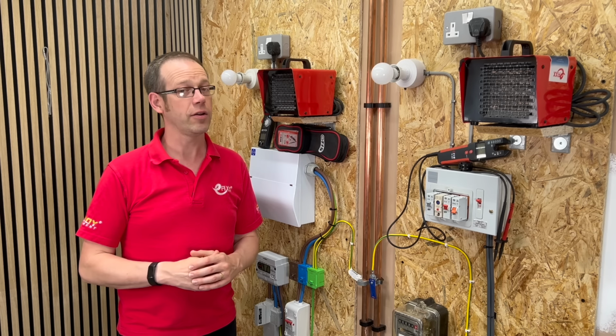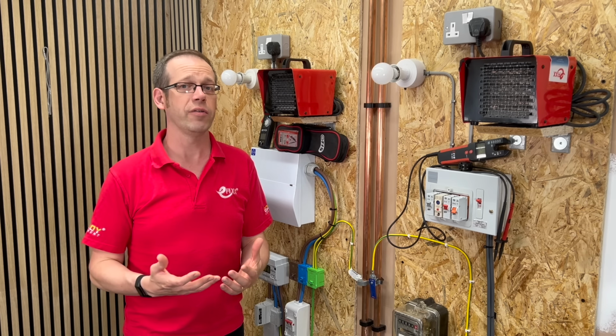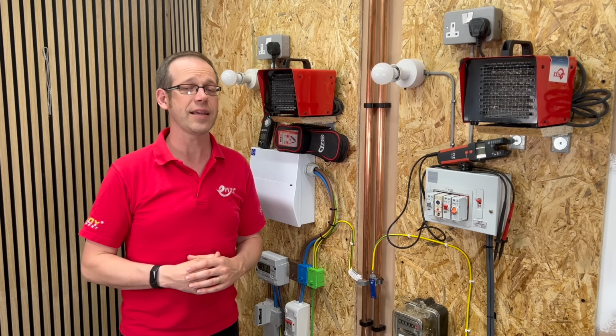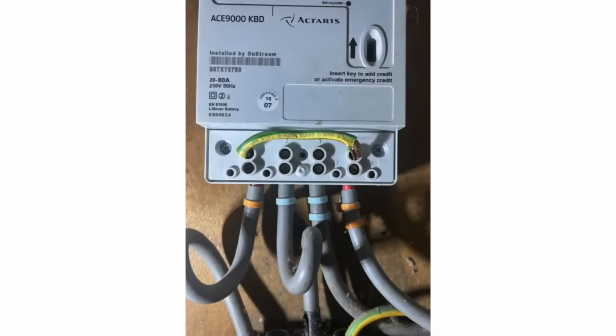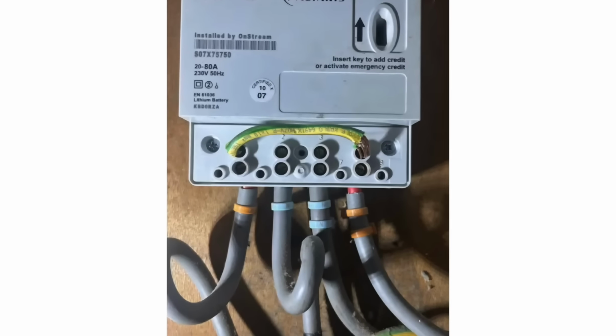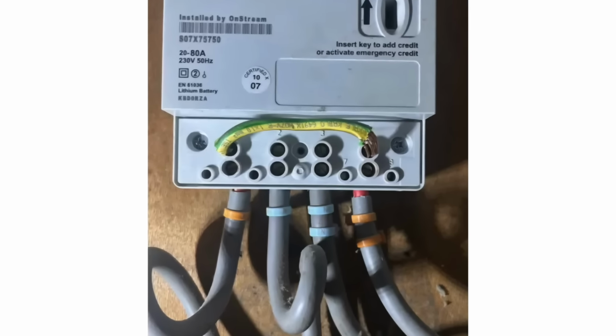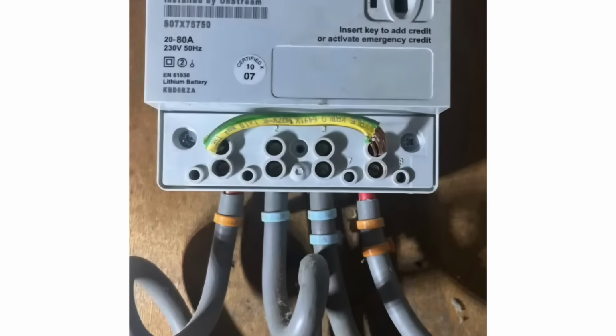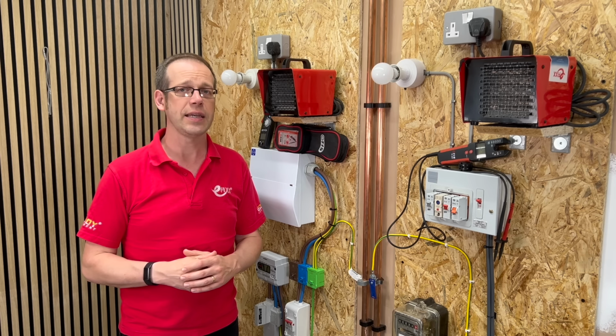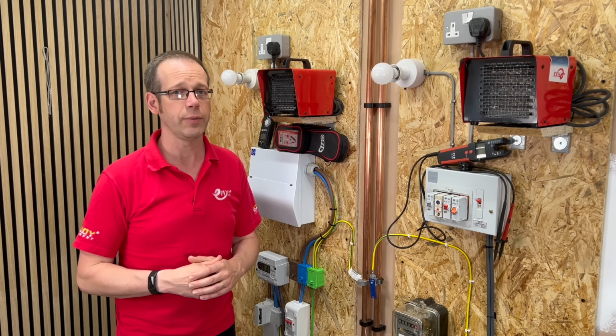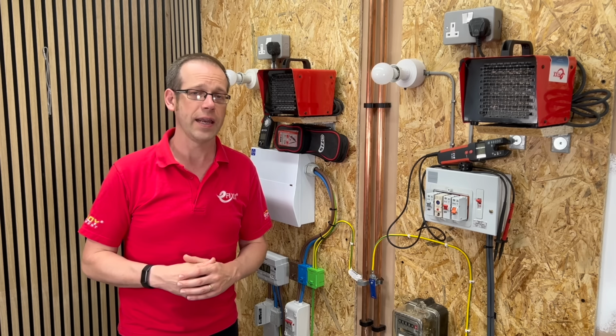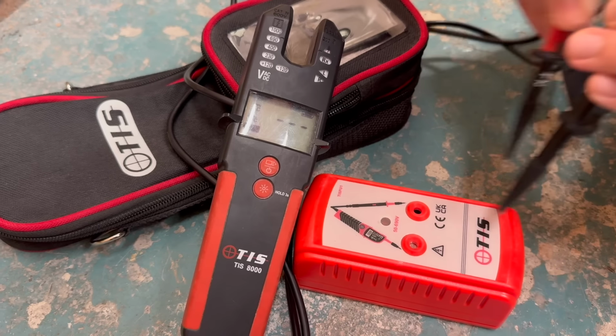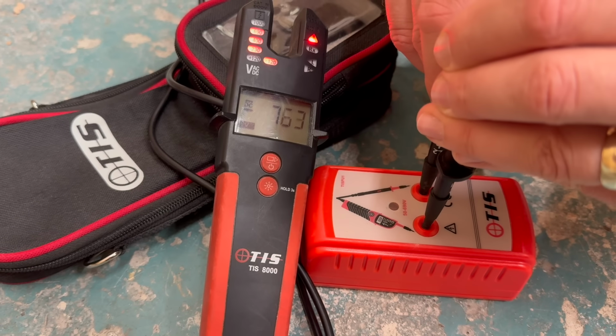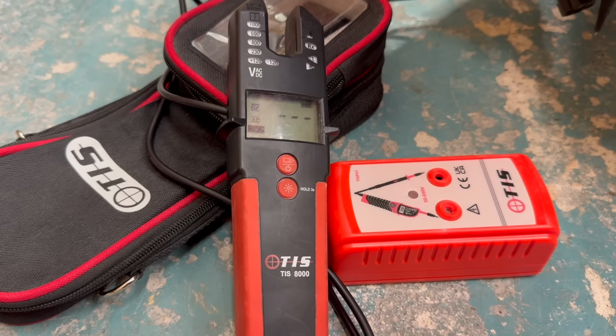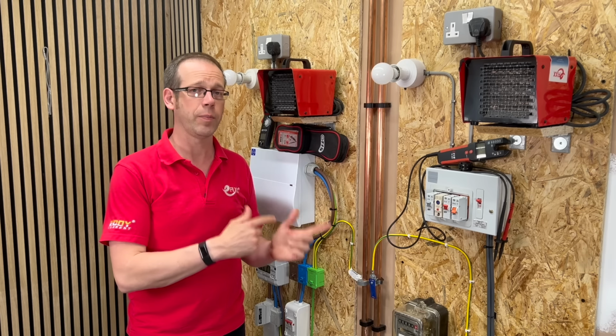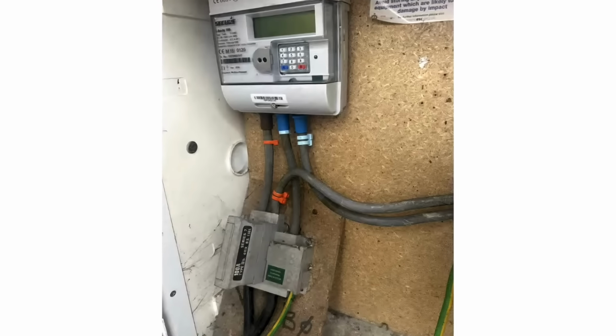Now, there's one final and often overlooked risk that electricians need to be aware of when completing safe isolation procedures, and that's the risk of energy theft, specifically through meter bypassing. This is a serious and growing crime where individuals tamper with or bypass the electricity meter to obtain energy without paying for it. Naturally, those who engage in this activity have no regard for regulations or electrical safety, which can create extremely hazardous conditions for anyone working on the installation. There have been documented cases where electricians carried out all the correct safe isolation procedures only to receive an electric shock from a backfed circuit, a result of a bypassed meter supplying power outside of the expected paths.